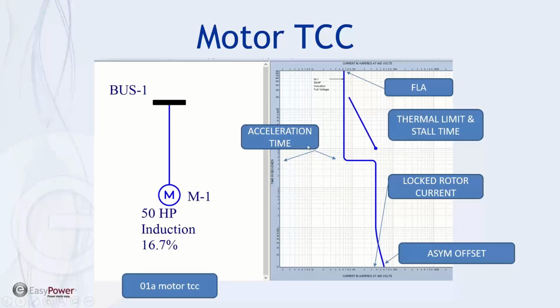But what we're looking for, first of all, is acceleration time. Once we apply across the line voltage, the motor is at a standstill. That's referred to as a locked rotor condition. And so where this vertical line extends down and intersects our axis, that's referred to as locked rotor current. And that current will be normal or acceptable until the motor is accelerated. So the time of this particular cross member is referred to as acceleration time. So it looks like we have an acceleration time of about 5 seconds on this motor and a locked rotor current of looks like 4,000 amps.